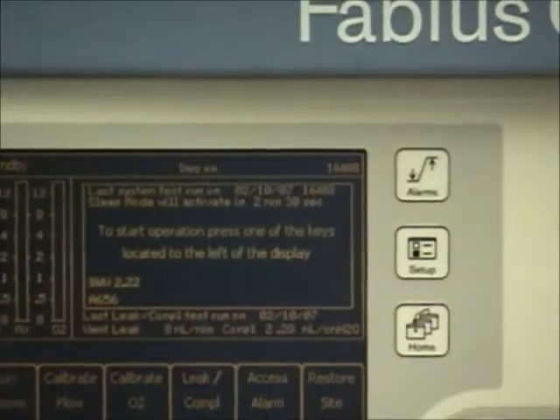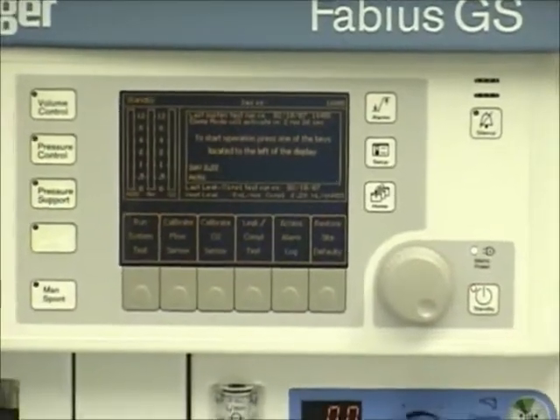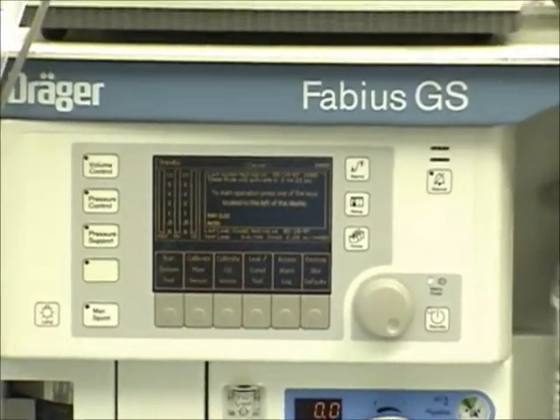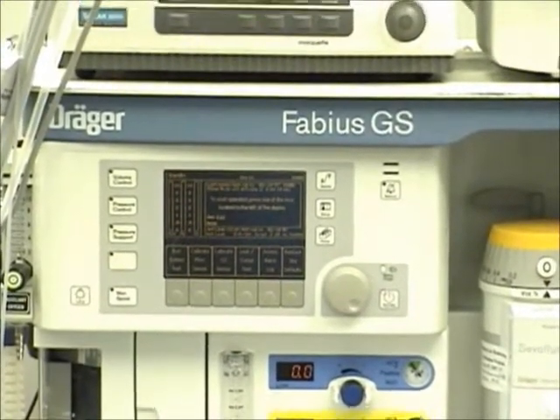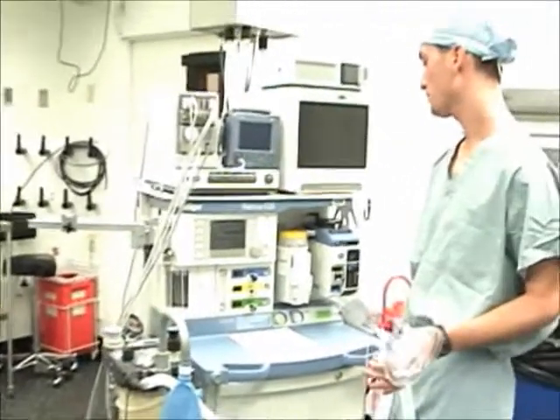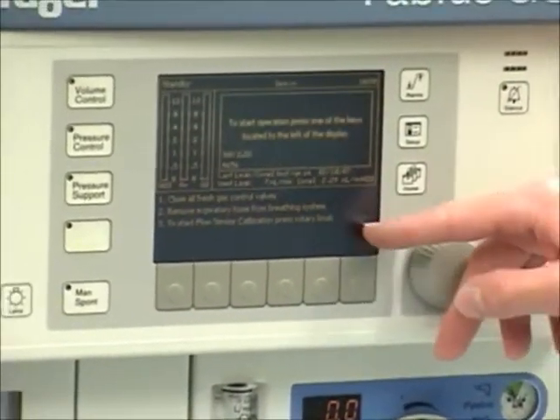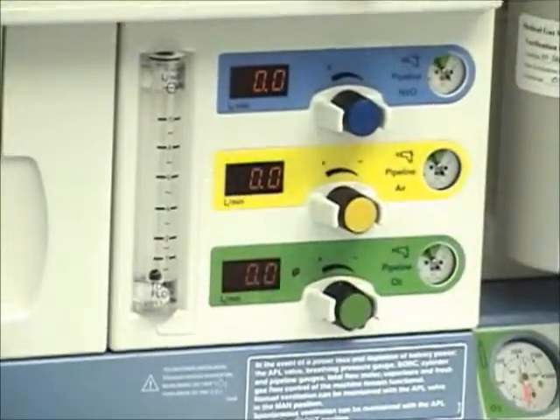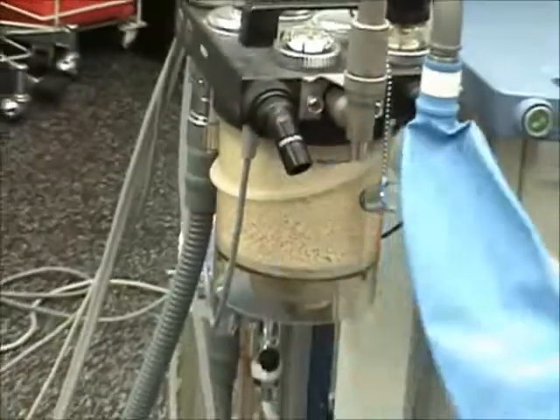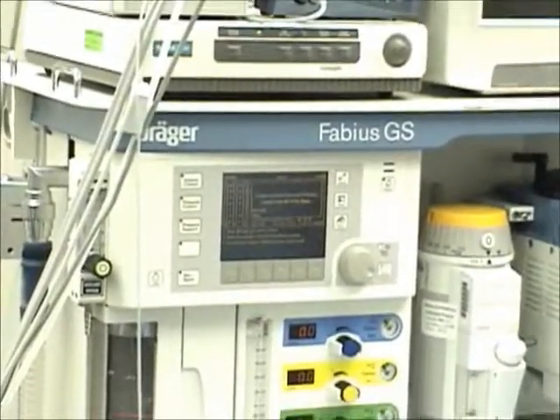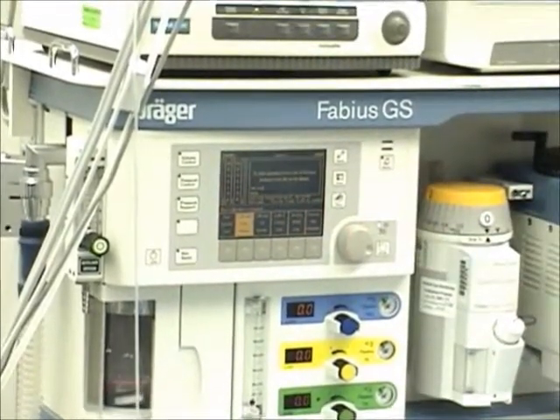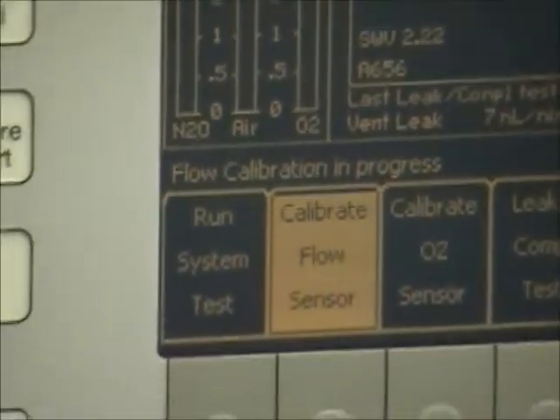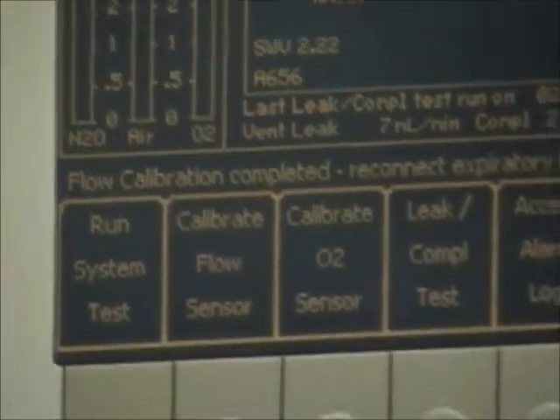A passing system test ensures the software and internal electronics are functional and that the reserve power battery has at least 95% charge. This provides 45 minutes of machine operation time in the event of AC power failure. Perform a flow sensor calibration by pressing the corresponding soft key and following the instructions on the LED display. 1. Close all fresh gas control valves. 2. Remove expiratory hose from breathing system. To start flow sensor calibration, press rotary knob. Flow calibration in progress. Flow calibration completed. Reconnect expiratory hose.